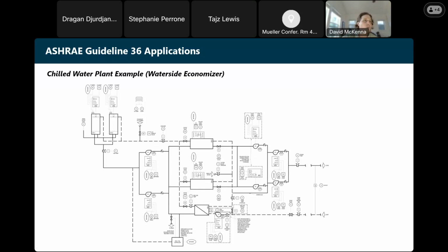And then sometimes, depending on your climate zone, we may also see a water side economizer, which is essentially a fluid to fluid heat exchanger that lets you bypass your chillers. So you don't need to run the compressor. When the outside air temperatures and water temperatures are optimal, we don't need to be producing cold water, because the water coming back from the cooling towers is actually cool enough to provide what we need to the building. And when we have all these sensors within the system that are able to monitor and control those conditions, we can use those to our benefit and ultimately save building energy.